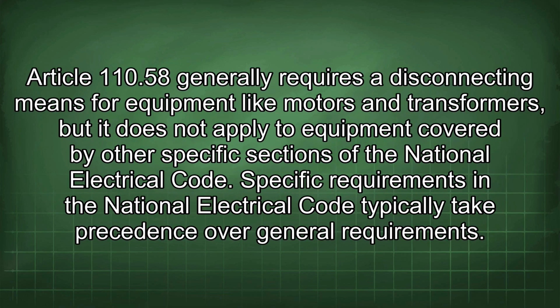Article 110.58 generally requires a disconnecting means for equipment like motors and transformers, but it does not apply to equipment covered by other specific sections of the National Electrical Code. Specific requirements in the National Electrical Code typically take precedence over general requirements.